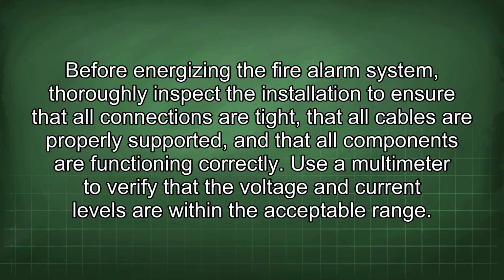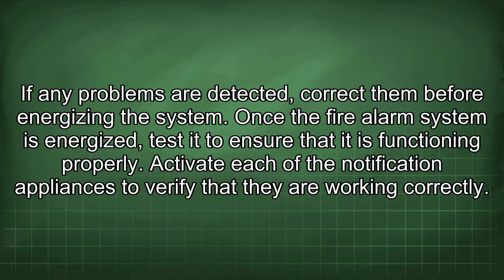Before energizing the fire alarm system, thoroughly inspect the installation to ensure that all connections are tight, that all cables are properly supported, and that all components are functioning correctly. Use a multimeter to verify that the voltage and current levels are within the acceptable range. If any problems are detected, correct them before energizing the system.